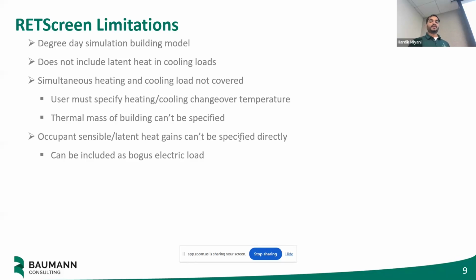Occupant sensible and latent heat gains are not taken into consideration. It can only estimate the heat being rejected by lamps or electrical equipment, from sensible loads, but depending on the occupancy in the building, it cannot determine the sensible and latent load rejected by the occupants in the space.